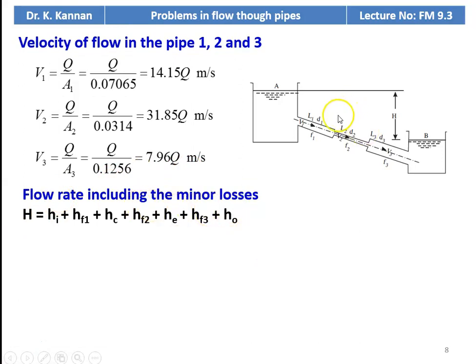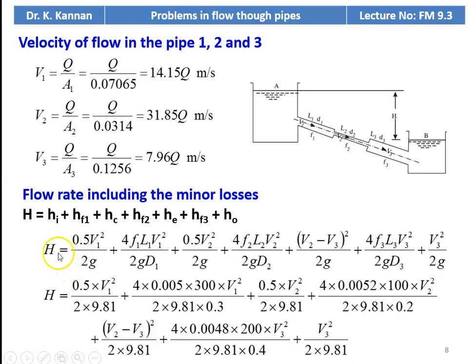For flow rate including minor losses in the compound pipe, the total head loss H = Hi + Hf1 + Hc + Hf2 + He + Hf3 + Ho. Hi is the inlet loss, Hf1 is friction in pipe 1, Hc is contraction loss, Hf2 is friction in pipe 2, He is enlargement loss, Hf3 is friction in pipe 3, and Ho is the outlet/exit loss. The equations: Hi = 0.5V1²/2g, Hf1 = 4F1L1V1²/2gD1, Hc = 0.5V2²/2g, Hf2 = 4F2L2V2²/2gD2, He = (V2-V3)²/2g, Hf3 = 4F3L3V3²/2gD3, Ho = V3²/2g.